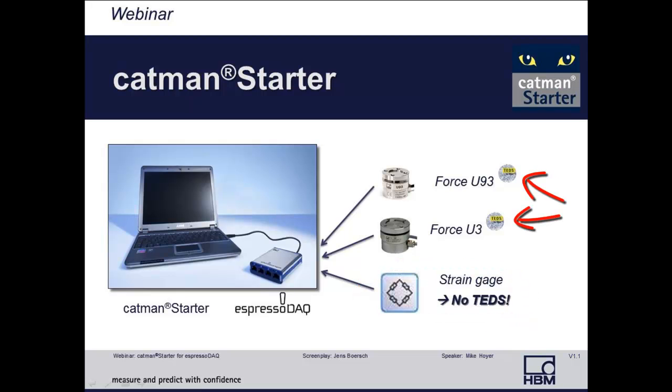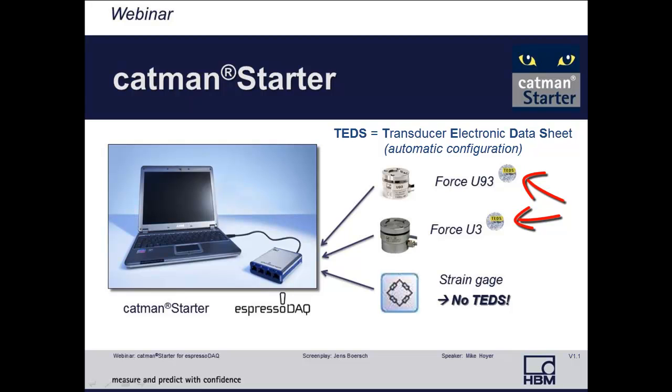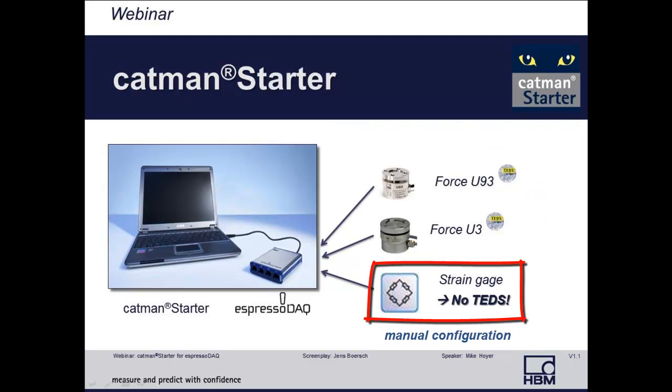Both force transducers are equipped with TEDS, an integrated transducer electronic data sheet, which will set up our amplifier automatically. Only the strain gauge does not include TEDS, so this will be set up manually.